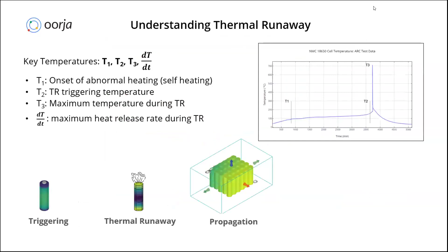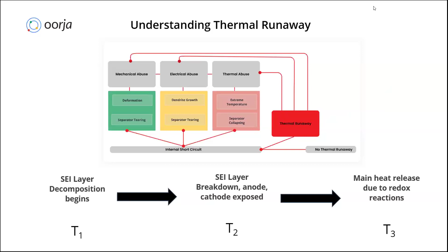There are three characteristic temperatures present in any ARC signature or thermal runaway signature of a cell. At T1, the onset of abnormal heating, the SEI layer decomposition starts. At T2, the thermal runaway triggering temperature, the SEI layer breaks down and the cathode and anode electrodes get exposed. At T3, the maximum temperature the cell reaches during thermal runaway, the main heat release due to the redox reaction happens.